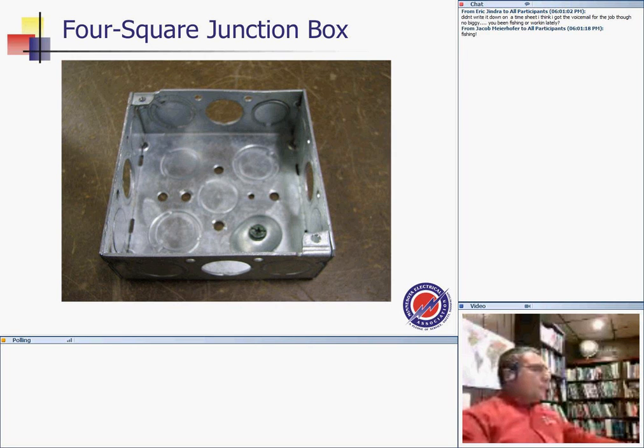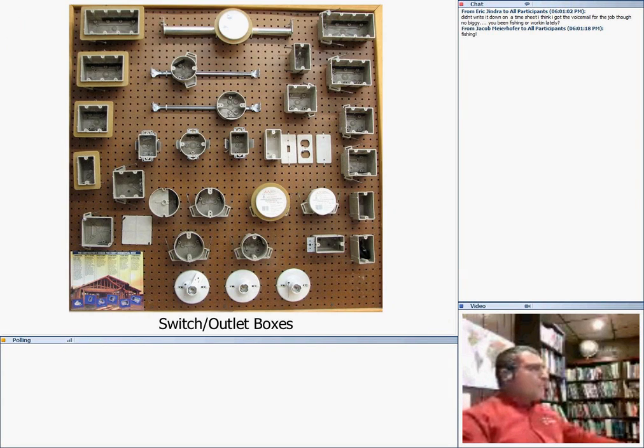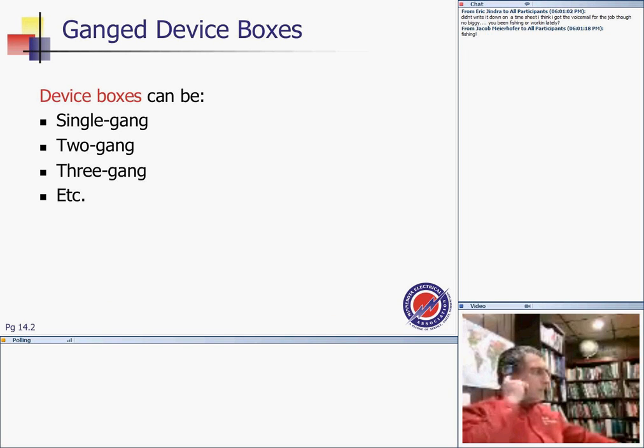Okay. You guys are familiar with the square boxes? Square boxes, these boxes, we're going to go look at them. Different types of boxes: gangable boxes, round boxes. This picture, as a matter of fact, is from our labs. Very visible. And you see the device boxes that you have over here, different multi-gang device boxes. I'm sure if you guys are doing your apprenticeship, here's a 4-gang device box, 3-gang device boxes. I'm not saying a lot of things that you guys don't know. Plastic boxes, metallic boxes, and so forth. Square boxes here that you can use. So these, for the most part, are device boxes. Round boxes too. Different types of round boxes that can be used to support a fan and so forth.